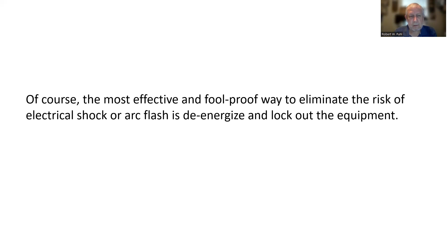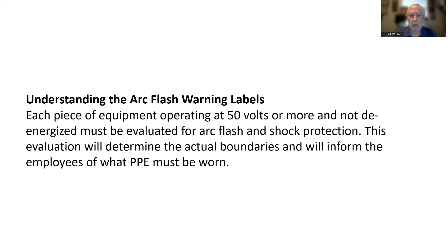Understanding the arc flash warning label: each piece of equipment operating at 50 volts or more and not de-energized must be evaluated for arc flash and shock protection. This evaluation determines the actual boundaries and informs employees what PPE must be worn. Once complete, an arc flash hazard warning label must be affixed to the equipment and readily accessible to employees who may work on it. If it's affixed to the equipment, it's right there in front of them.